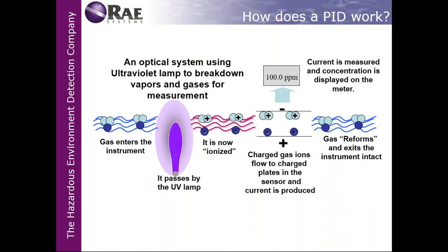So in other words, if you have gasoline on the left-hand side, it passes by the lamp, it creates a little poof or a little mini explosion. It's not dangerous by any means, but it just gets ionized. An electronic charge is produced.